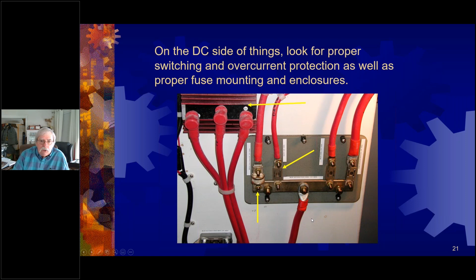Same boat. There's another view of that isolator. Battery switches. They all look pretty much the same. Some of them are orange. These happen to be gray. But what's really important is that they have a dual rating, a continuous rating and an intermittent rating. And yet, you can't really tell by looking at the face of the switch. The stud size on the back where the cables are connected is going to be very different depending upon their actual rating.